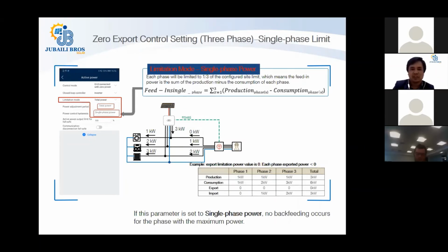The zero export control setting with the single phase limit. Now under the limitation mode you will have the single phase power option. If you select the single phase power option, no backfeeding will occur for the phase with the maximum power. So let's suppose in this scenario you have a 3 kilowatt load.